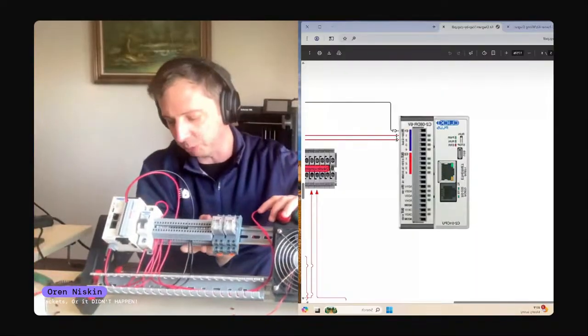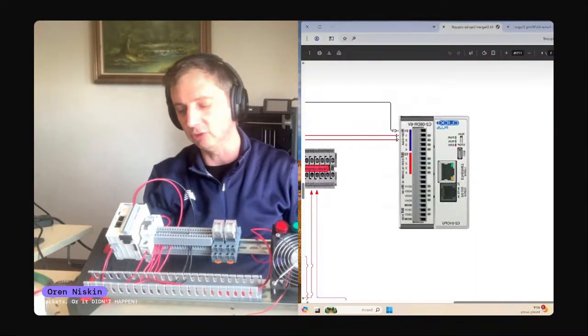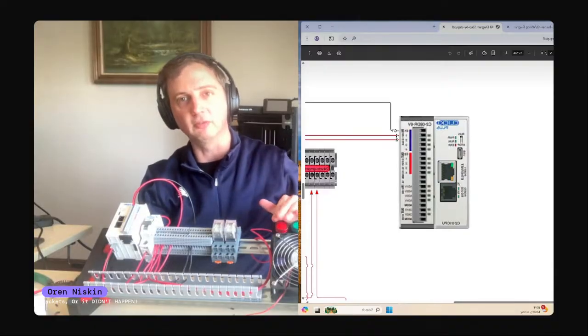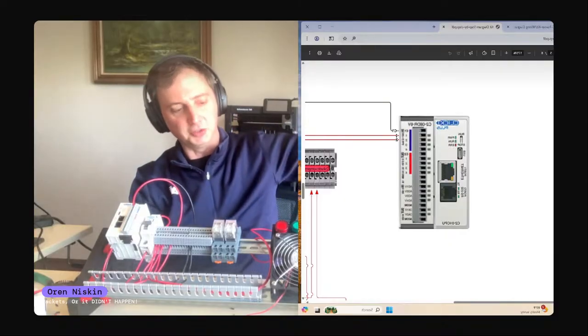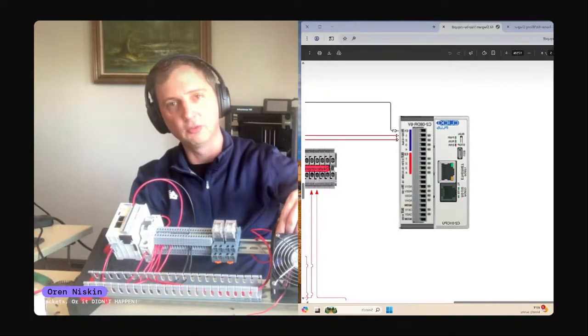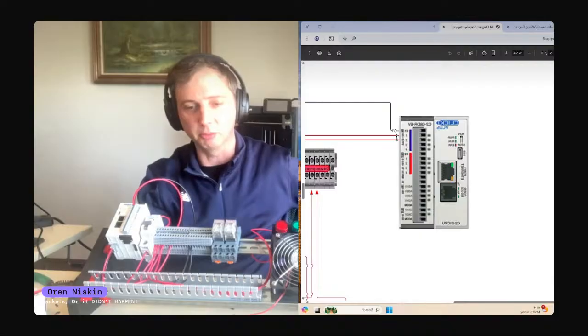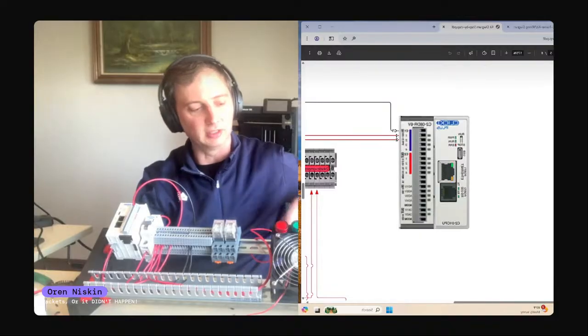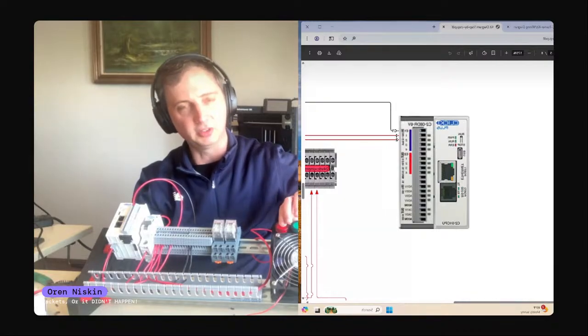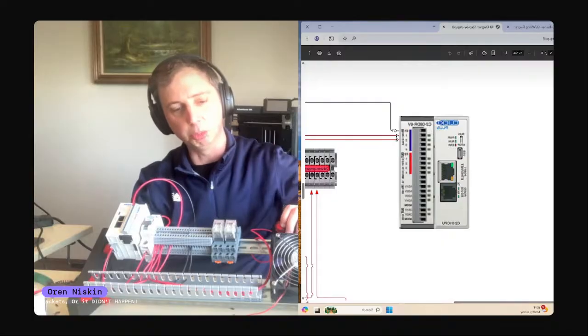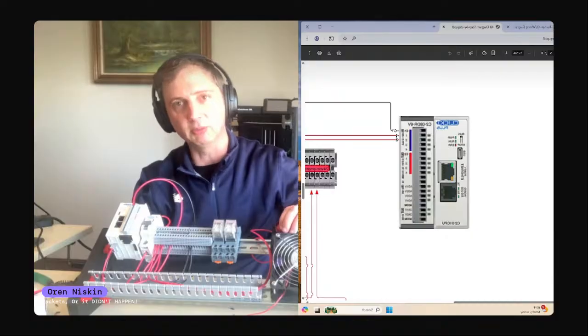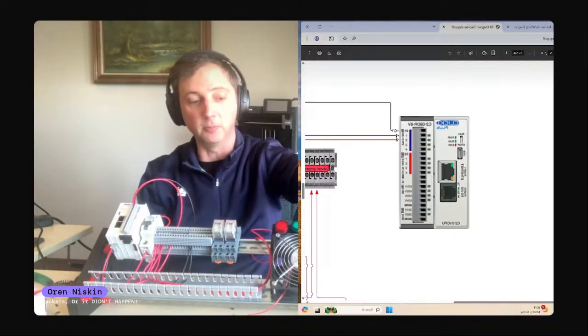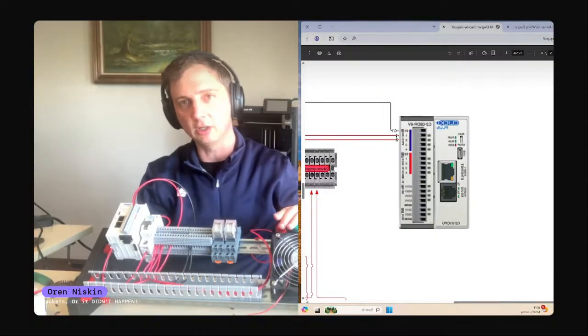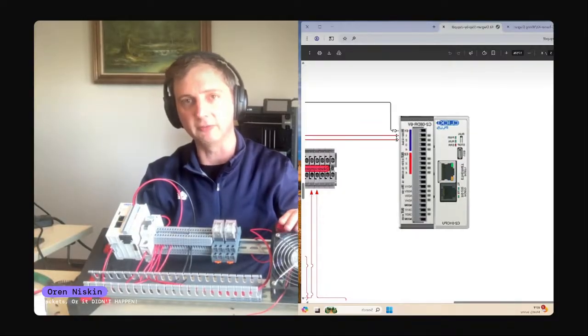This is pretty typical for stop buttons, because they've had issues in the past out in the field. Let's say this stop button is really far away—in real life it would be way out in the field. If somebody ran over that wire with something that cut it, like a backhoe, and then one day you wanted to stop whatever that was and pushed it, if it wasn't normally closed—if it was normally open—then when you pushed it, it would close the circuit for the button, but somebody had already backhoed it. So even though the button is closed, the backhoe created an open in the cable, so the motor would never stop. That's why they made it normally closed.